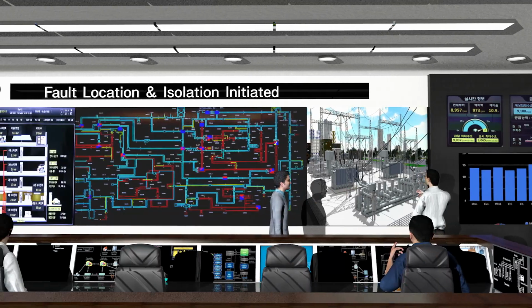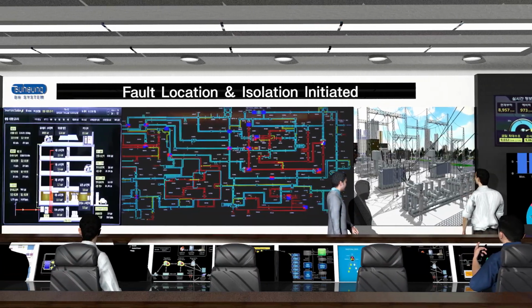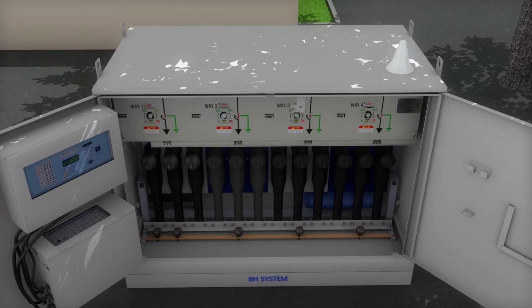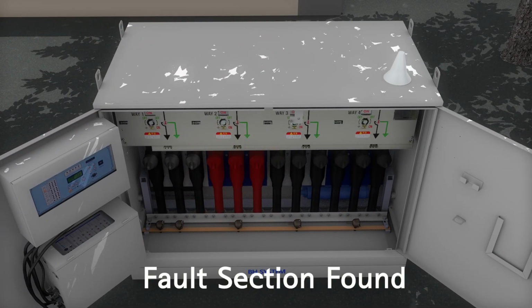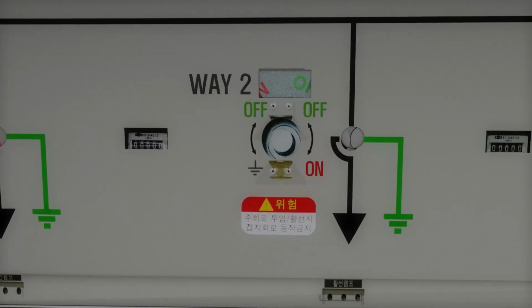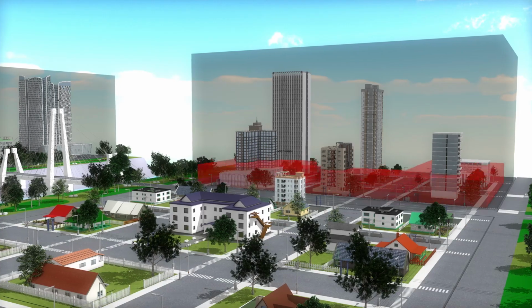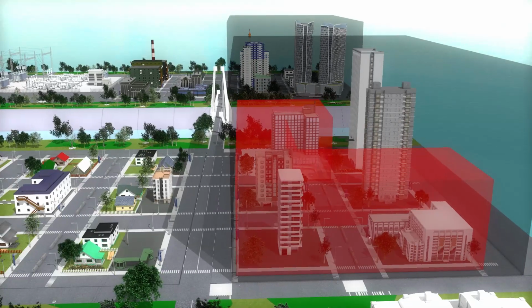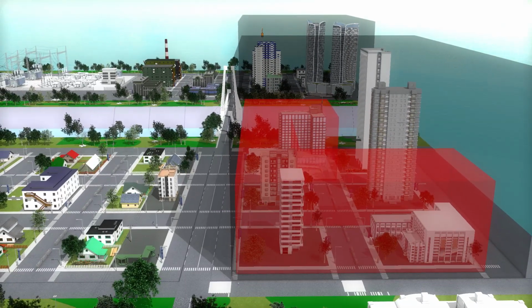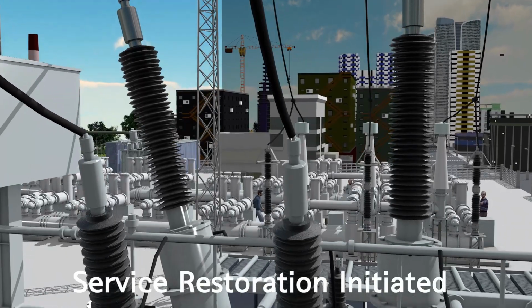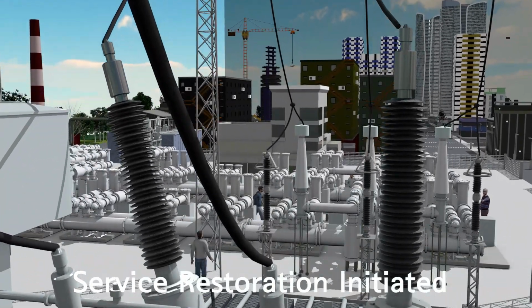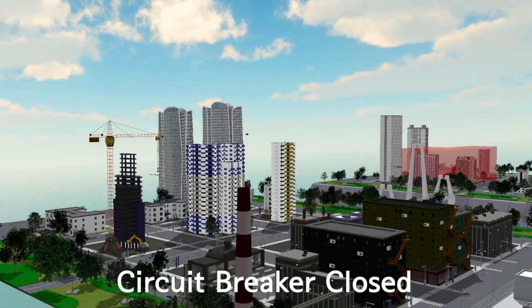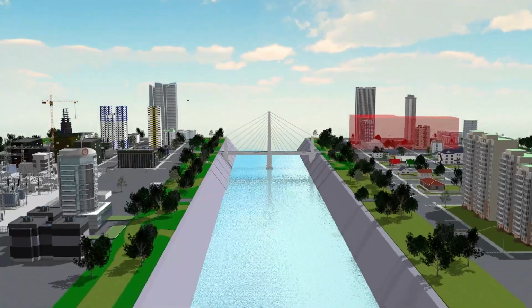The Distribution Control Center finds the faulty section based on information sent from the on-site equipment and isolates the faulty section from the system. After isolating the faulty section from the system, power supply will be resumed to the healthy section of the outage by closing the circuit breaker in the substation.